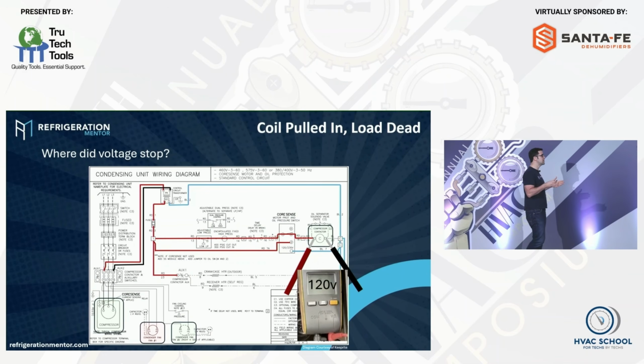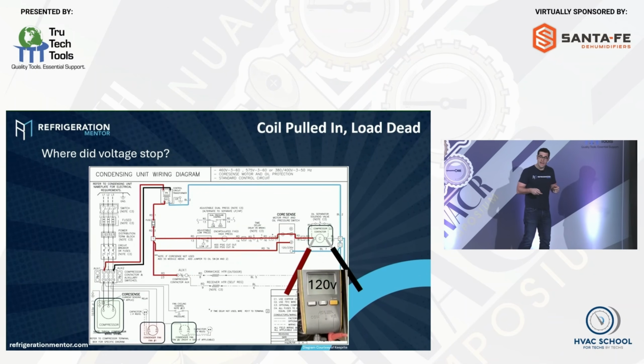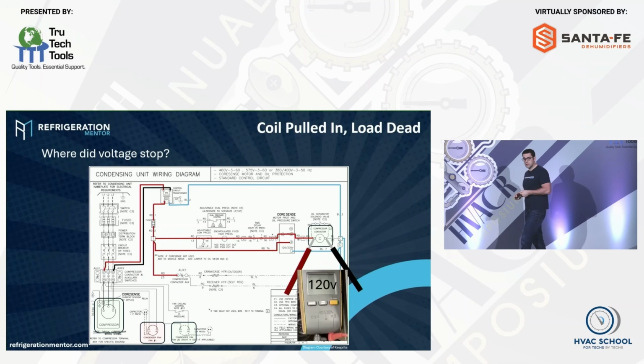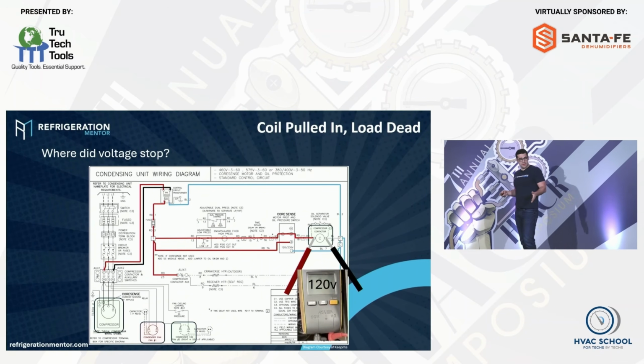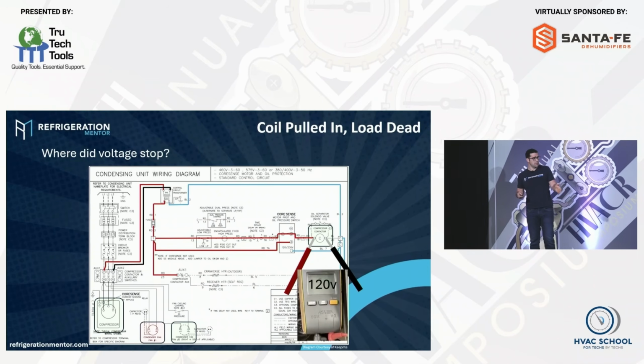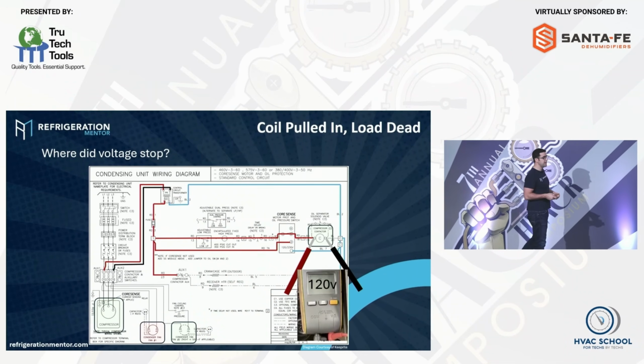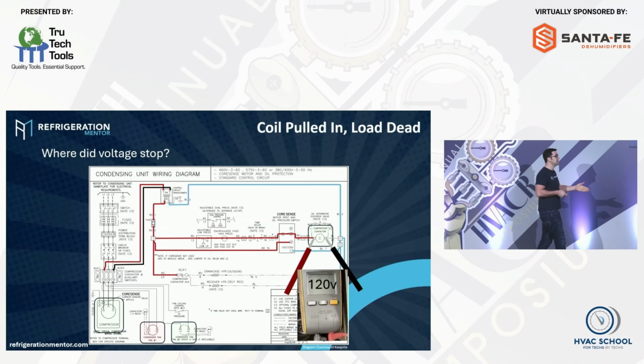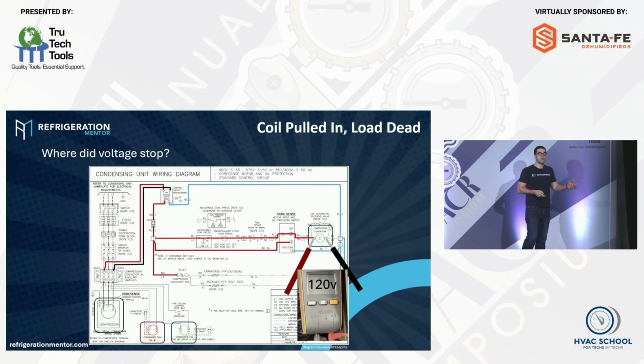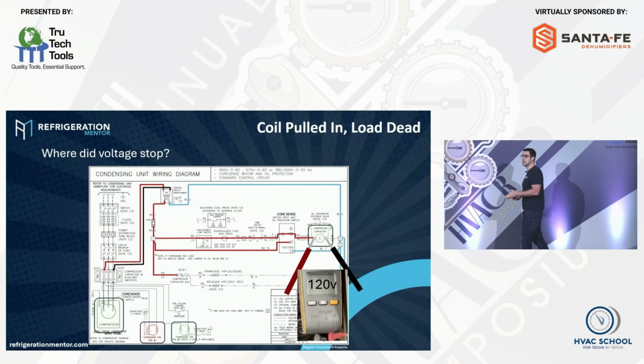Where did the voltage stop? This is so, so important. I have a coil pulled in, but the load is dead. For example, down here, you can't really see it right now, but the condenser fan is red down there. My coil's pulled in, but my fan is not working. Now we have to go to the root of the problem and check why that condenser fan is not working.